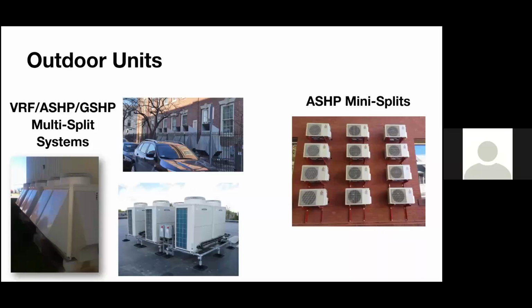And the reason for that is there are two reasons. One is because condensate does come from the bottom of these condensers, right? So if they're placed on grade, what happens at certain temperatures? Adam mentioned that 25 to 40 degree range. There's potential that condensate, if it's not drained properly, can start forming ice and building up to the point where it can get in the coils and crack the coils. And with a cracked coil, everyone's having a bad day. That's going to be a lot of phone calls. So make sure you get these units up on stands.